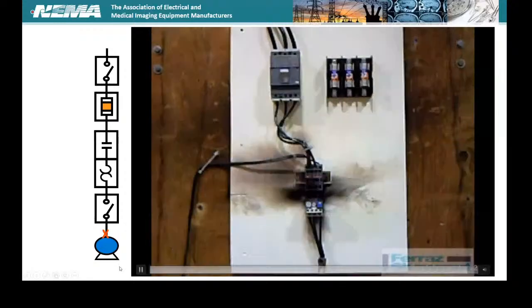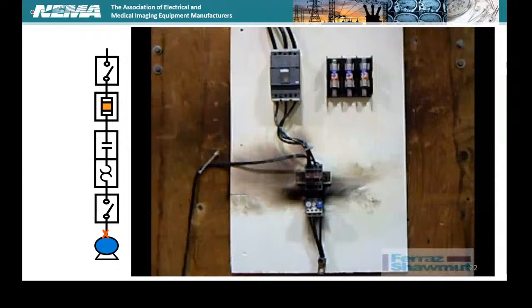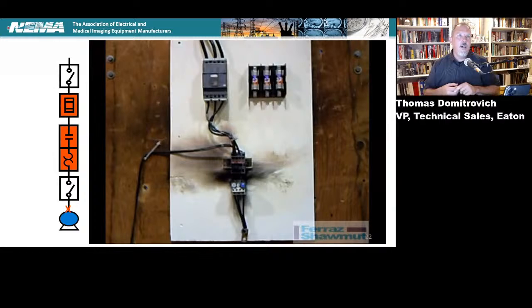You were breaking up there for me, but type 2 protection is what gets you the better coverage where you have no damage left. Type 1 protection is what you're seeing here, where it still will pass the test because you're allowed to have damage, and it's just the extent of damage that they try to control. When you use a type 2 type of application, that means that you're not going to have the amount of damage that you see.